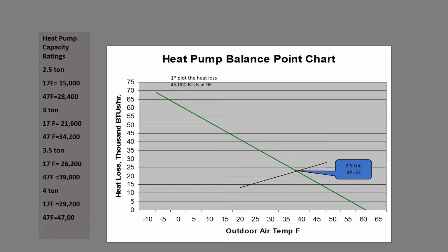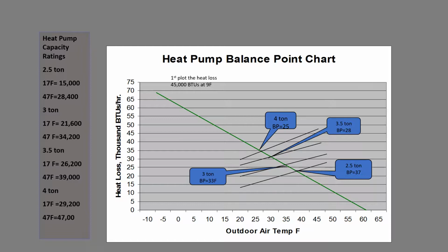Let's plot our 2.5 ton system. So there's our capacity. We've simply drawn a line between capacity at 17 degrees and the capacity at 47 degrees. In this case, that 2.5 ton system would have a balance point of roughly 37 degrees. Too high for our wants. Let's see what a 3 ton comes in. 3 ton comes nicely in at 33 degrees. Let's see what a 3.5 will give us. 3.5 down to 28. That would make it a really good choice for the PTCS program. Sure, we could go larger, we could go 4 tons, but you know, it's going to cost more money. It might not add that much economic benefit, and the ducts probably aren't big enough to handle that much air.